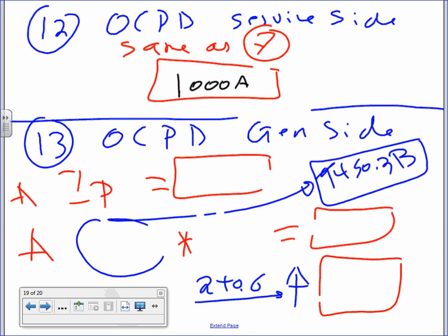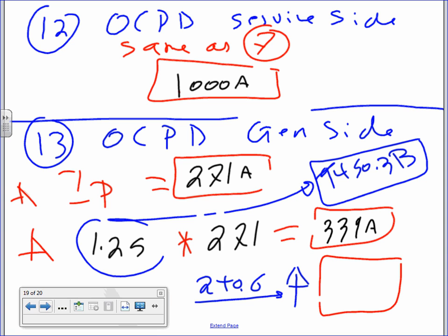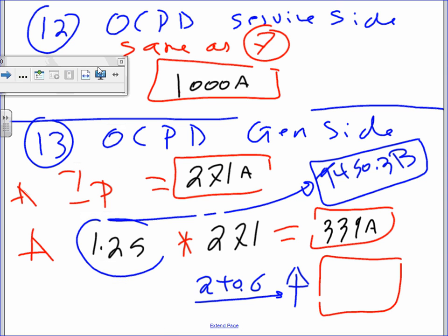For conductors on the generator side, you take the 271 amps, remember, that's from the transformer. Then you multiply it by 1.25 from the transformer calculation, Table 450.3(B). Multiply 271 amps by 1.25, and that will get you 339 amps. Then you take your 339 amps to 240.6, and that goes up to 350.